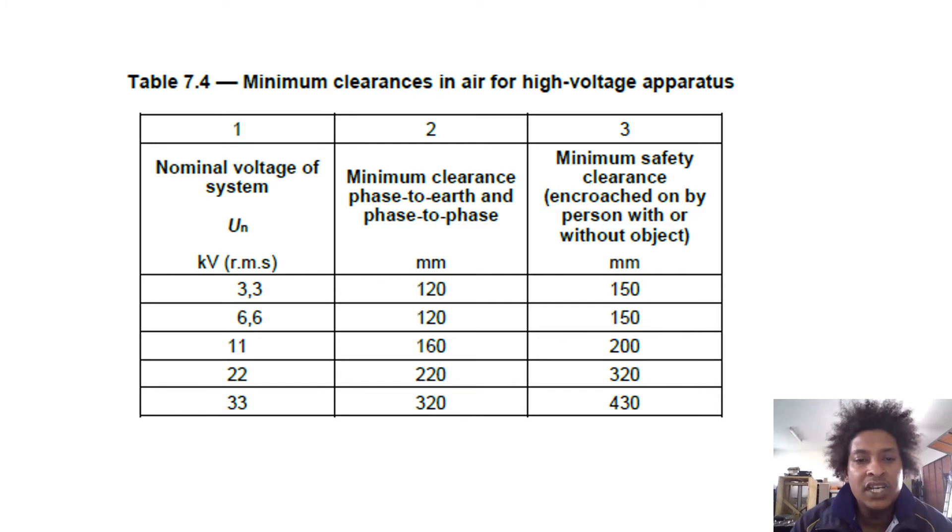At 22 kV, the phase clearance is 220 mm and the person-with-or-without-object clearance is 320 mm. At 33 kV, the phase clearance is 320 mm phase-to-phase and phase-to-earth.